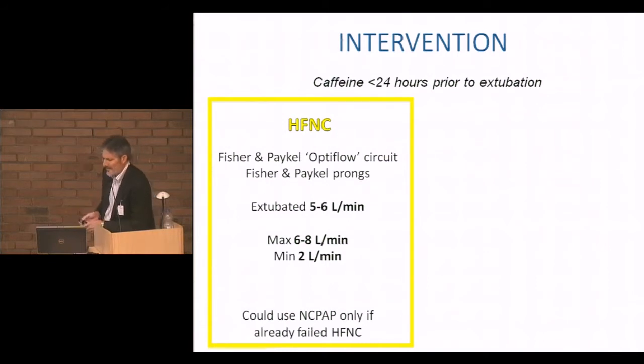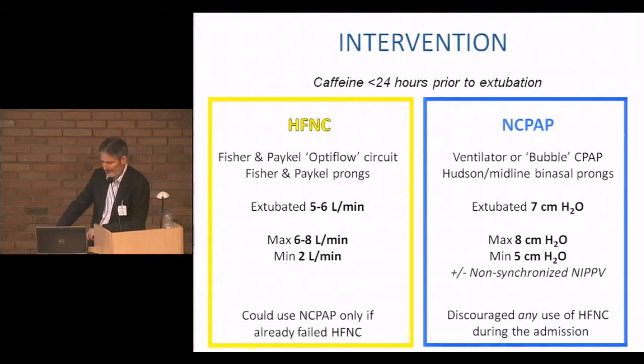So the flow that you use through each of these prongs depends on the size of the prongs, and that is determined by the size of the baby. So for the biggest prongs, you can go up to 8 litres per minute. For the smallest prongs, only 6 litres per minute. We said that if you reached failure criteria and you were randomised to the high flow group, you could use nasal CPAP. So you could rescue babies with nasal CPAP if they'd failed high flow.